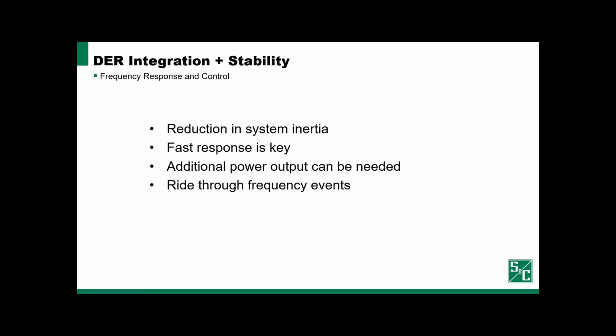With rotating machines being displaced by inverter-based resources, we have a reduction in system inertia. We have less rotating mass to compensate and absorb these changes, which results in faster changes in frequency when we have a system event. Consequently, it's imperative that our resources respond very rapidly to frequency changes in a low inertia system that we expect with highly penetrated DER systems, as well as inverter supplied microgrids, or microgrids in general are typically low inertia.